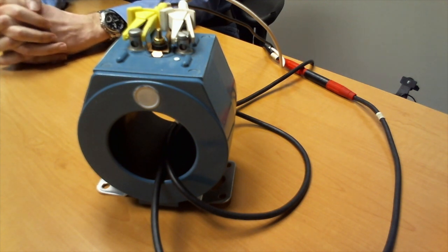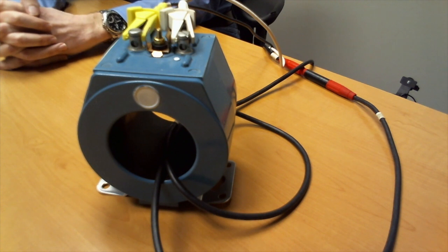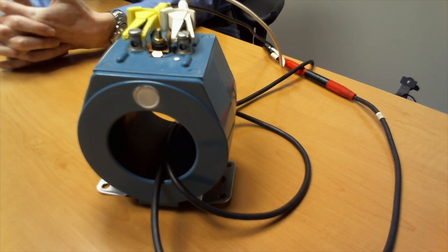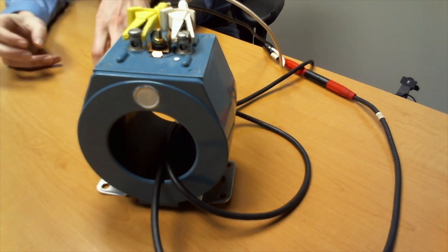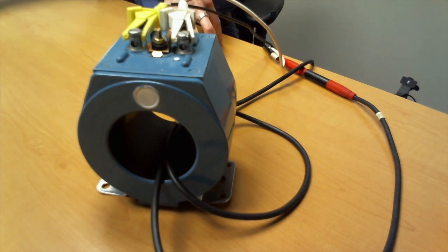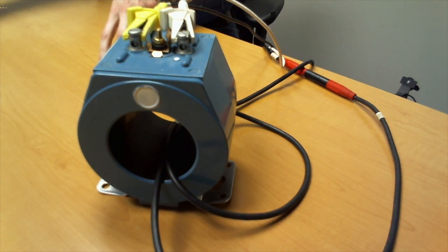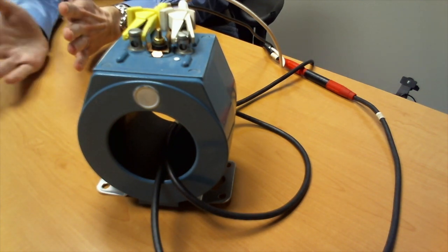Nick is correct that these CTs do cost more, but if you think about it, I've been to a lot of meter shops and I've seen on the shelf 200s, 400s, 600s, 800s, 1200s, all on their shelf, where you can almost replace it with 1 or 2 CTs just by going with these extended range, high accuracy class CTs. So yeah, I'm a big proponent of high accuracy extended ranges, mostly because I'm kind of nerdy that way. I like the characteristics and studying of instrument transformers.